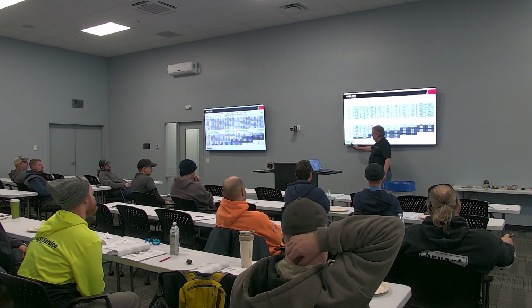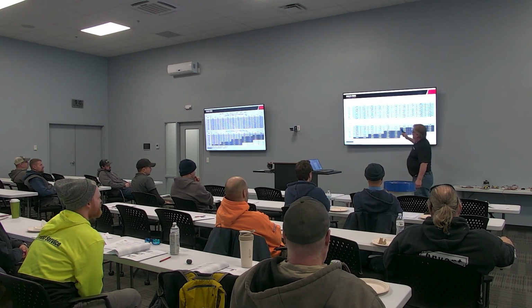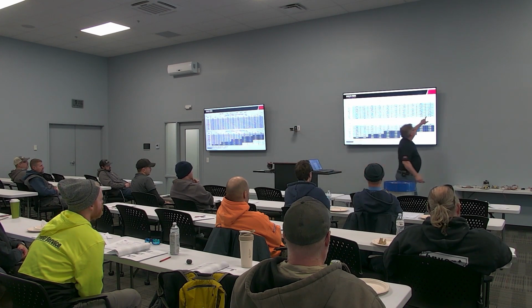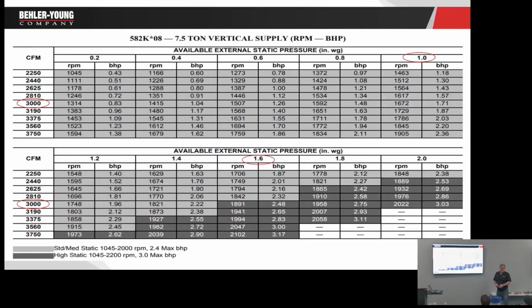The gray is standard and medium static units. The dark gray is high static units. Remember, the difference is going to be the motor, the whole blower assembly. So let's say I need 3,000 CFM, and I have 1 inch of static. That works. But what if I have 1.6 inches of static? Okay, this is the max that standard static unit can do, is 1 inch.